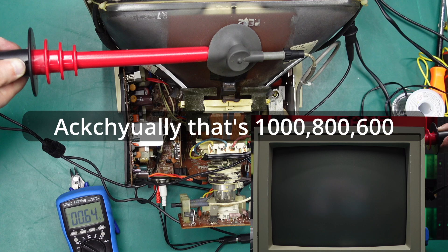If I turn this all the way down, so the screen's basically black, we go up to 25.03, and bringing the contrast and brightness all the way up, we hit 24.19, 24.2. So that is a difference of about 800 volts compared to 2200 on the other CRT. Power that off, watch the high voltage drop. 1000 volts, 800, 600. So yeah, big difference between this flyback and the one in the other monitor.